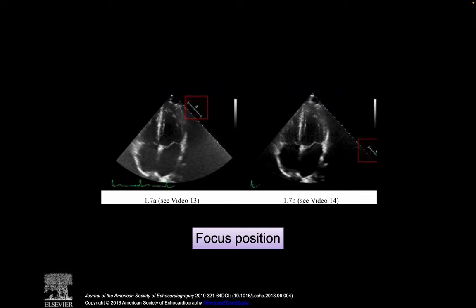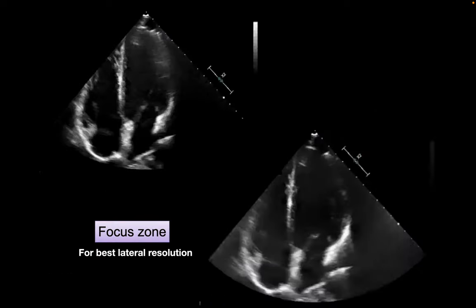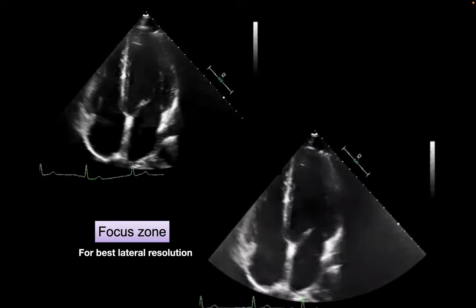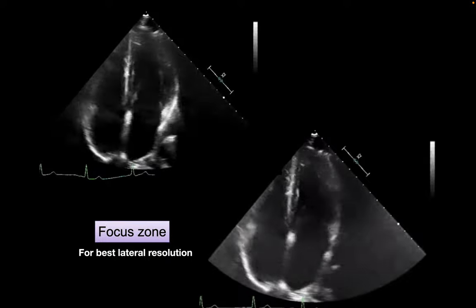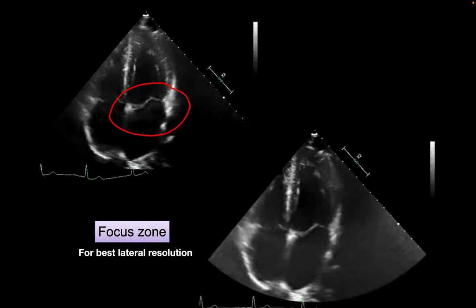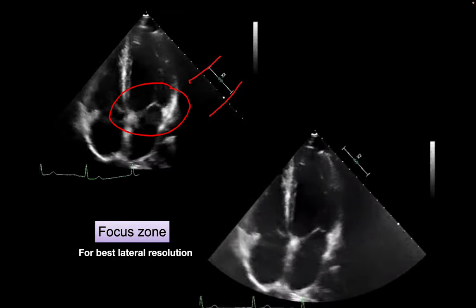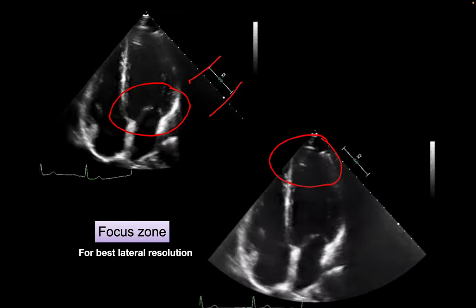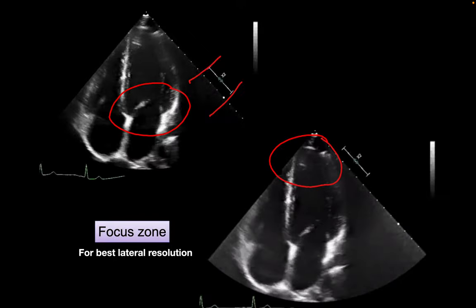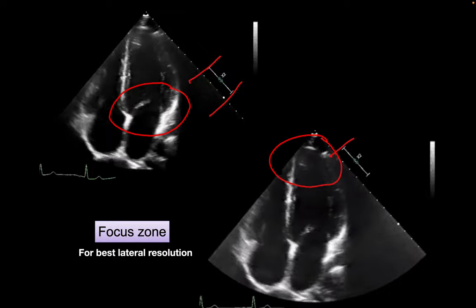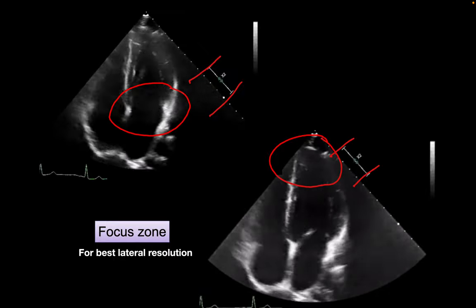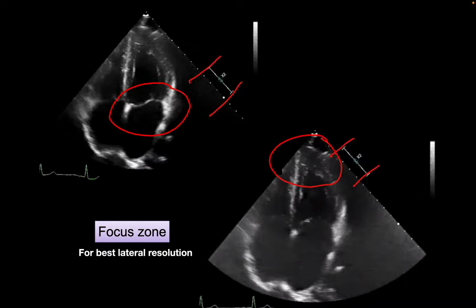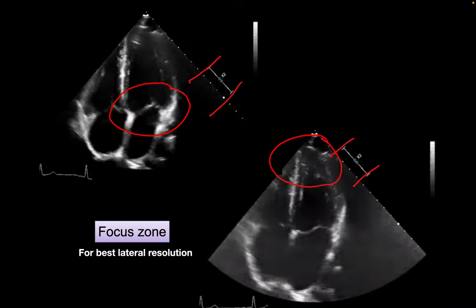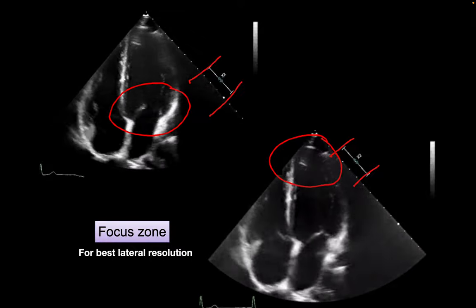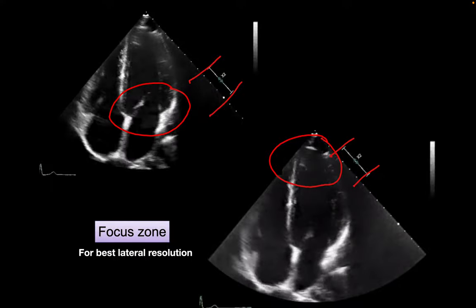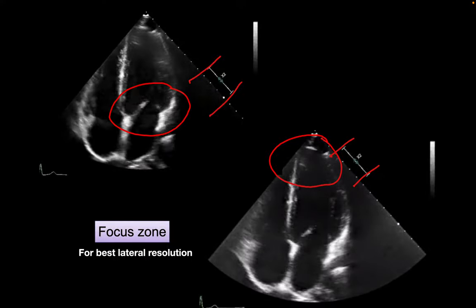Focus position and the focal zone, really. So we should always change the settings according to what we are looking at. For example, if you're more interested in the mitral valve area, then you set your focal zone to that depth. If you're more interested in the apical area and you're looking for an apical thrombus, then you set your focal zone for that. That's really just to improve your chances to identify various abnormalities and really to get the best resolution for that part of the image.